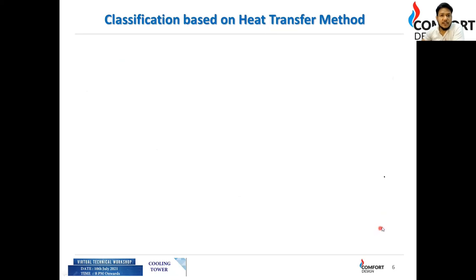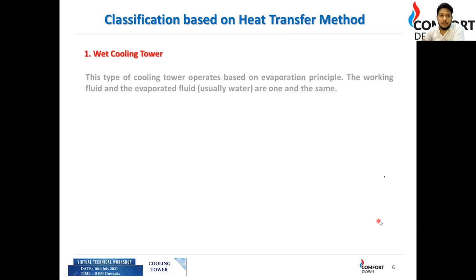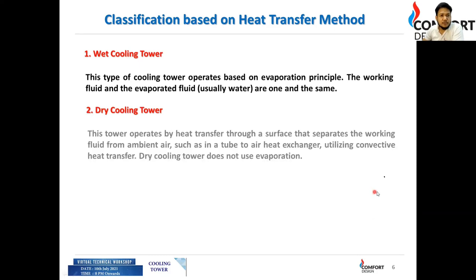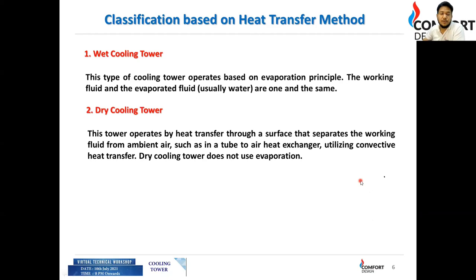Moving to classification based on heat transfer method: a wet cooling tower operates based on the evaporation principle — water is evaporated and heat transfer occurs through that. A dry cooling tower operates by heat transfer through a surface separating the working fluid and ambient air, such as in a tube-and-air heat exchanger. It uses convective heat transfer and does not use evaporation.